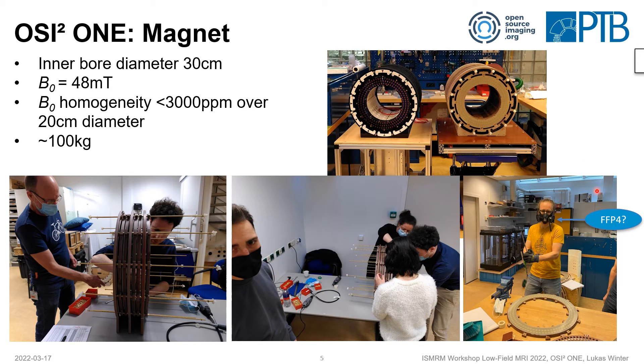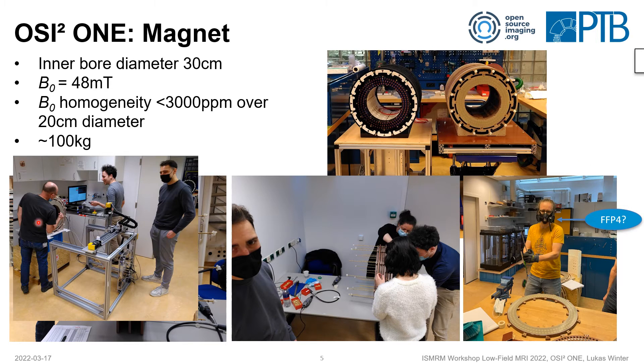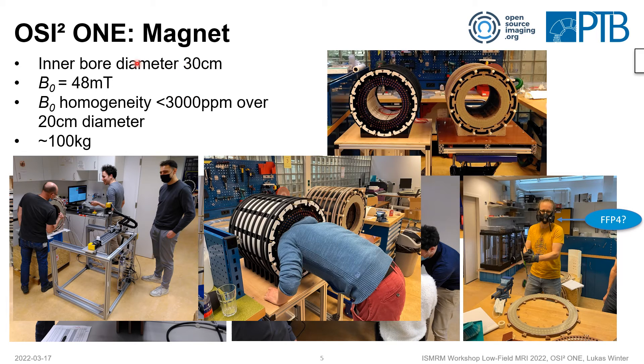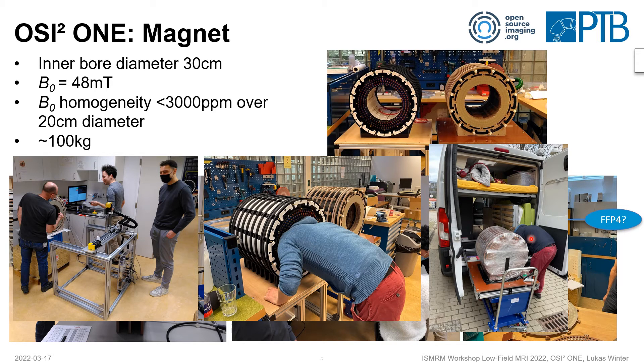There were other challenges, not only COVID as you can see here, but also faulty magnets and different material tolerances. The good news is that after building this magnet and mapping the field, we reach very similar field strengths of 48 millitesla, which also comes out of simulations. We have homogeneity below 3,000 ppm over 20 cm in diameter, which is promising. The head fits inside the 30 cm inner diameter bore, the whole system is around 100 kg, which makes it relatively easy to pack into a camper and drive 700 km from Leiden back to Berlin without damage.